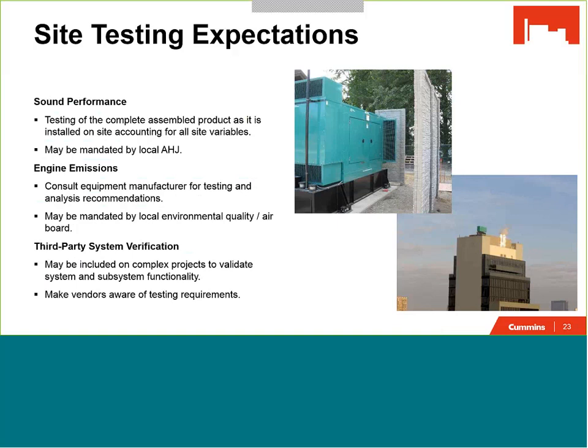And so a site test is only going to be there to verify the performance of the product as it is installed. It's also going to be done in order to account for things that the generator set manufacturer couldn't account for during prototype testing, like additional walls or acoustical barriers that are installed on site. Emissions is another area where we're seeing more and more on-site testing with commissioning of products. This is typically mandated by some local authority or air board. Again, just be aware that this may be a requirement in your particular facility.